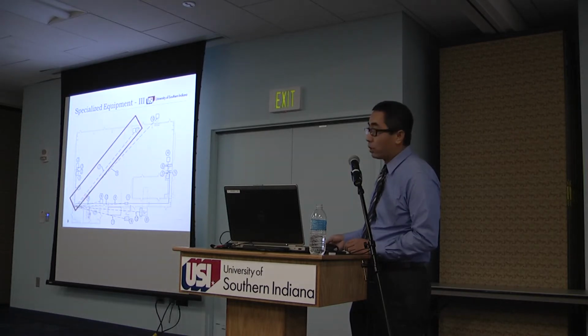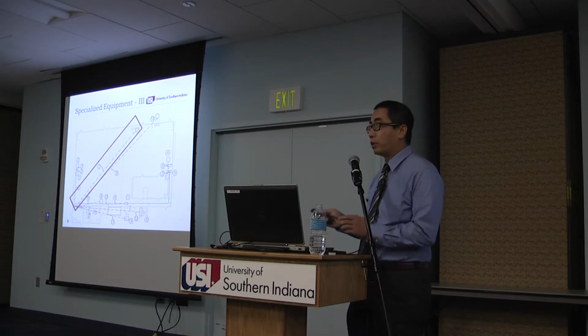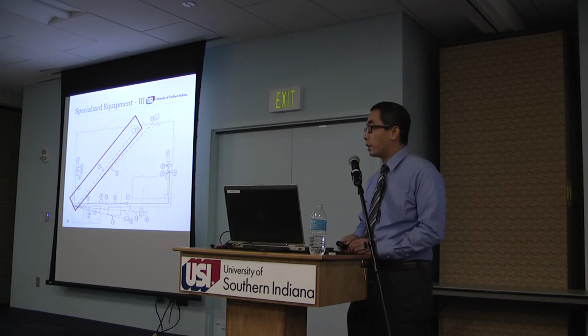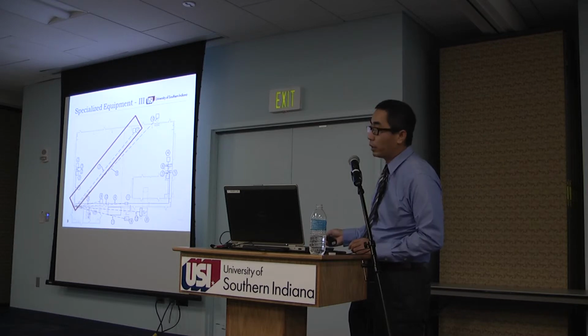So this drawing shows what we call the raceway. Basically, how you run your wire from the service entrance to the equipment you need. The one we just looked at is our service entry from this point down. So we have the 1-inch PVC all the way up to here, to supply the power for the brake frame.